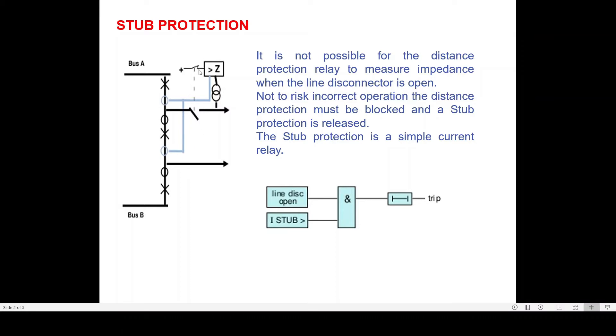But what protection are you using? You are using the distance protection, and that distance protection is already out of service because of the missing CVT input. So this portion becomes unprotected. To protect this section you need a protection system that does not depend upon voltage and which will perform isolation of faults immediately. The only possible method available is overcurrent protection. It is not possible for the distance protection relay to measure impedance when the line disconnector is open. To avoid the risk of incorrect operation, the distance protection must be blocked and a Stub protection is released.